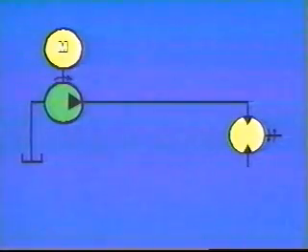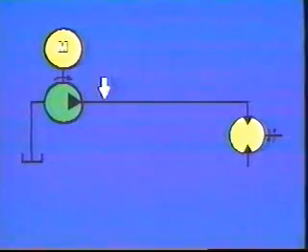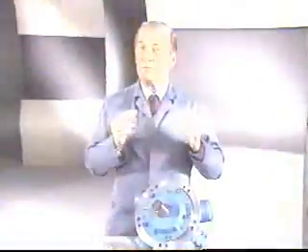Oh, you say, wait a minute. Let's put a relief valve in this line. A relief valve doesn't have to be anything more than a ball held on a seat by a spring. You just tighten up on the spring until it's harder to push the ball off its seat than it is to drive the motor with its normal load. Overloading the motor would cause the ball to lift off its seat and divert the pump flow back to the tank, permitting the pump and electric motor to run even though the hydraulic motor is stalled.